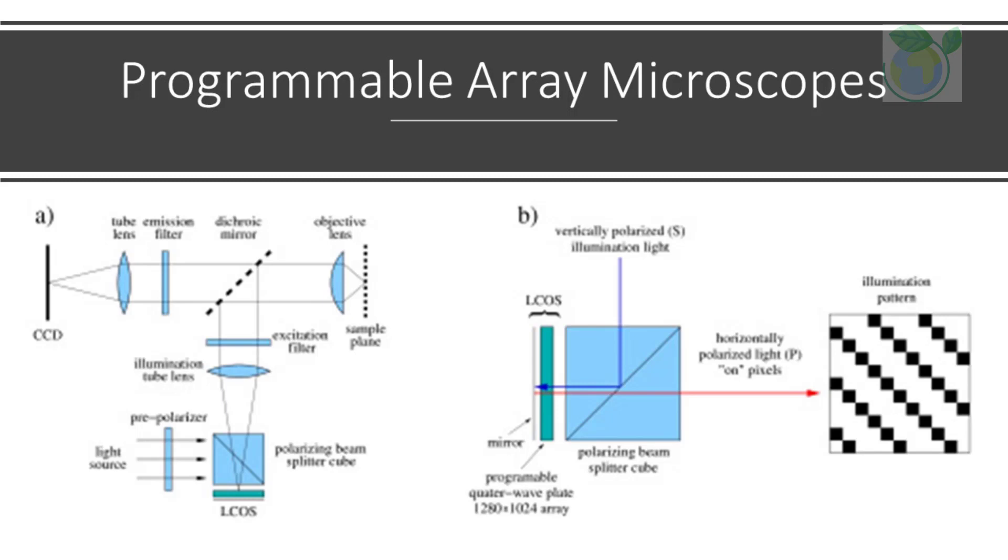Programmable array microscopes, termed as PAM, use an electronically controlled spatial light modulator, termed as SLM, that produces a set of moving pinholes. The SLM is a device containing an array of pixels with some property—opacity, reflectivity, or optical rotation—that can be adjusted electronically. The SLM contains microelectromechanical mirrors or liquid crystal components. The microscope's illumination tube lens and objective collect the light from pixels in the ON state and image the microdisplay onto the sample. Subsequently, the image is usually acquired by a charge-coupled device, CCD, camera.